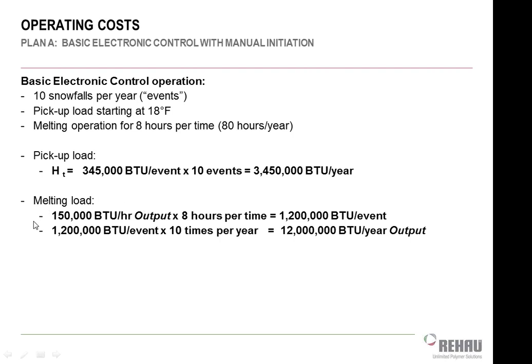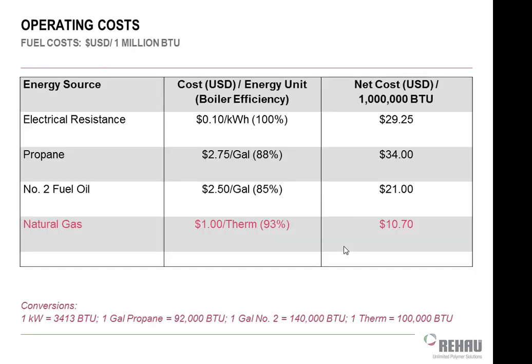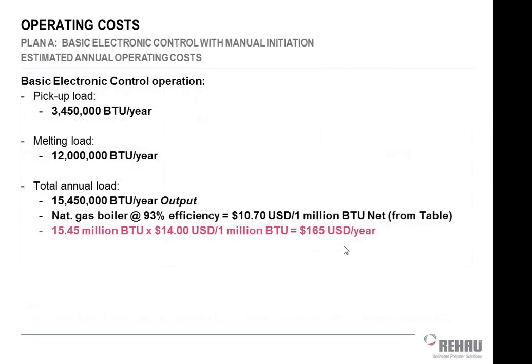Then I've got the load of actually melting the snow, right? So that's 150,000 BTUs per hour based on that layout that we had a minute ago, times 8 hours per incident. That's 1.2 million BTUs per event, times 10 events. So that's 12 million BTUs. So altogether, it's 16 million BTUs per year to run the snowmelt system with that type of control. So that's the 15 million there.